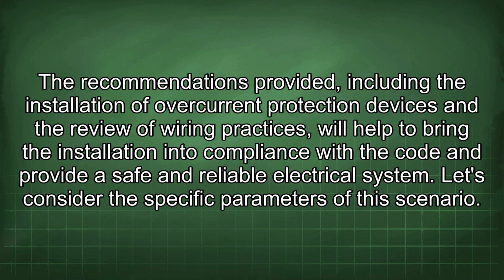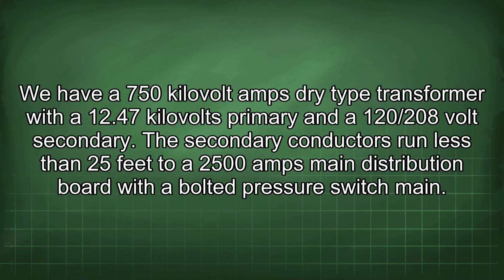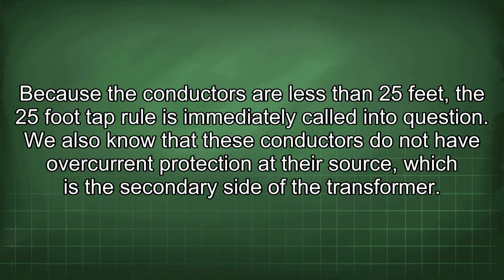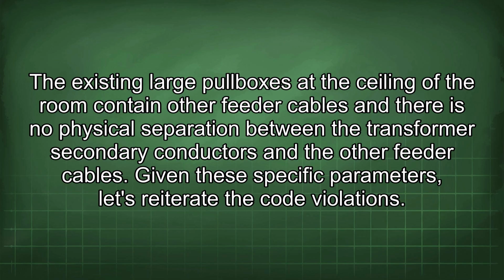Let's consider the specific parameters of the scenario. We have a 750 kVA dry-type transformer with a 12.47 kV primary and a 120/208 volt secondary. The secondary conductors run less than 25 feet to a 2500 amp main distribution board with a bolted pressure switch main. Because the conductors are less than 25 feet, the 25-foot tap rule is immediately called into question. We also know that these conductors do not have overcurrent protection at the source, which is the secondary side of the transformer. The existing large pullboxes at the ceiling of the room contain other feeder cables, and there is no physical separation between the transformer secondary conductors and the other feeder cables.